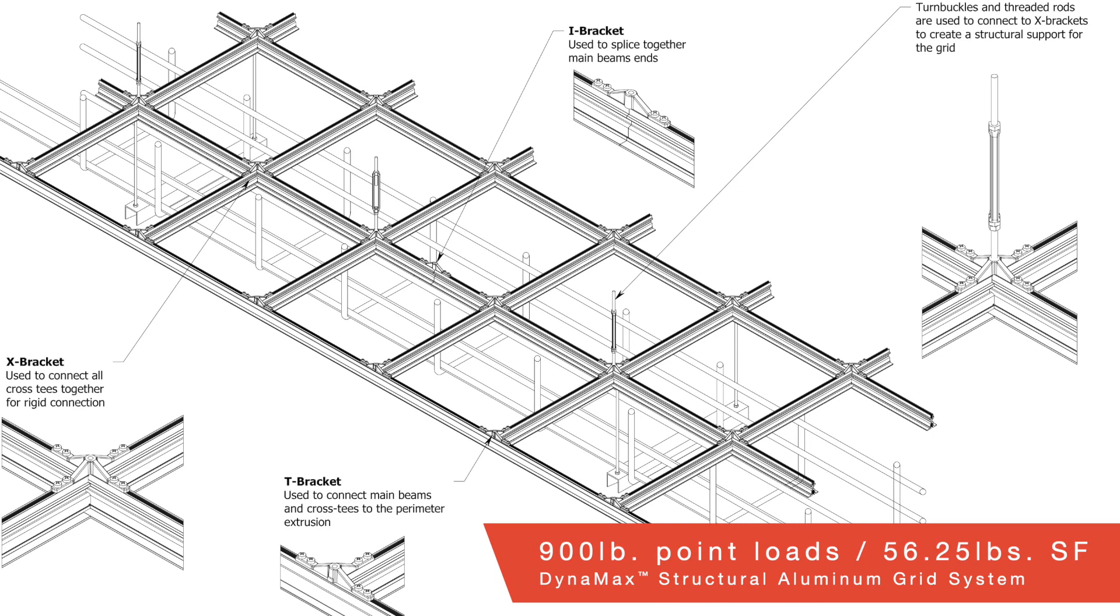DynaMax supports up to 900 pound point loads or 56.25 pounds per square foot when loads are suspended with 3 eighths inch threaded rod at four foot by four foot connection points.